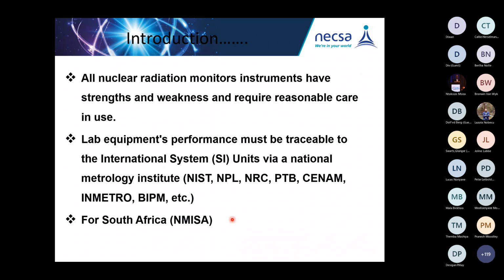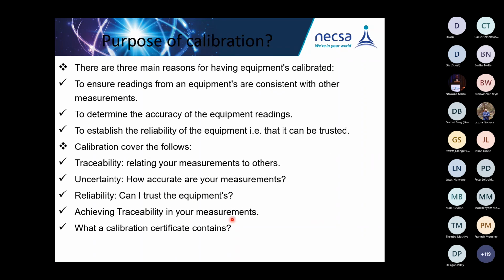If the instrument is not calibrated by NMISA, it means that lab has already broken the chain of traceability, in a way that measurements cannot be trusted. Why are we supposed to perform calibration? There are three main reasons for having the instrument calibrated, to ensure readings. We're not doing this for the regulatory body to see that we are complying, because we don't want to burn our fingers. We're not doing this to please the regulatory body.